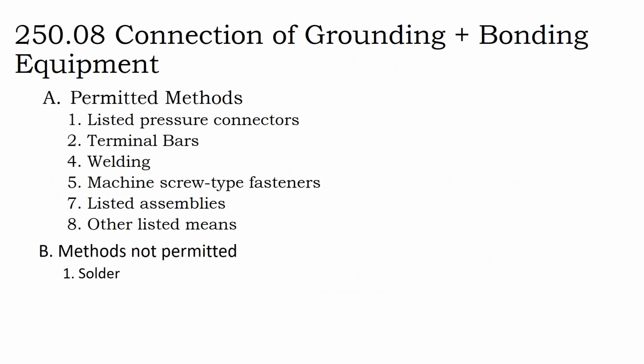One thing that I can think of that you might need to check is when you're in areas of more compact soil types. We were driving the ground rod in our off-grid home, and in Mississippi, you get this rock shelf underneath your soil. And so that was preventing the ground rod from going all the way down to depth. And you're allowed to angle it and eventually lay it down on its side. But the problem is, beyond this concrete barrier of soil, there might only be 3 feet of additional mud. Well, this mud is pretty dense too, and it's more insulating than conductive.